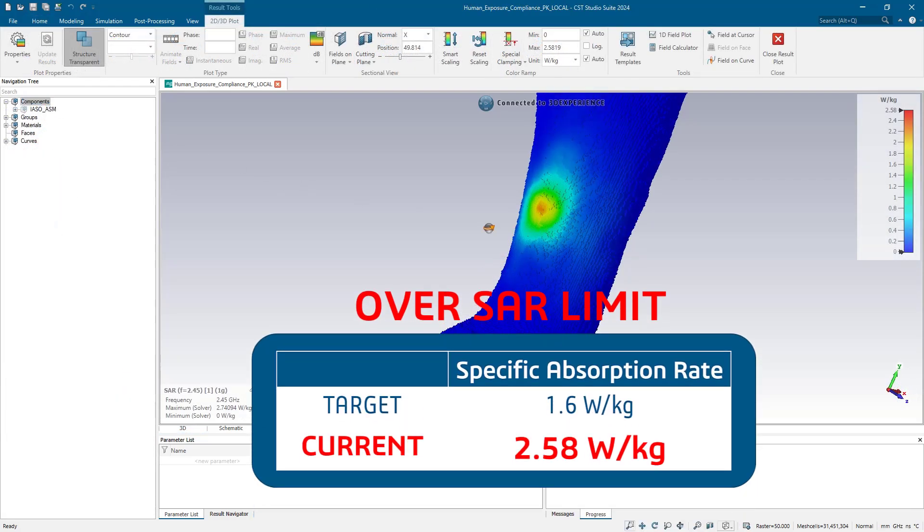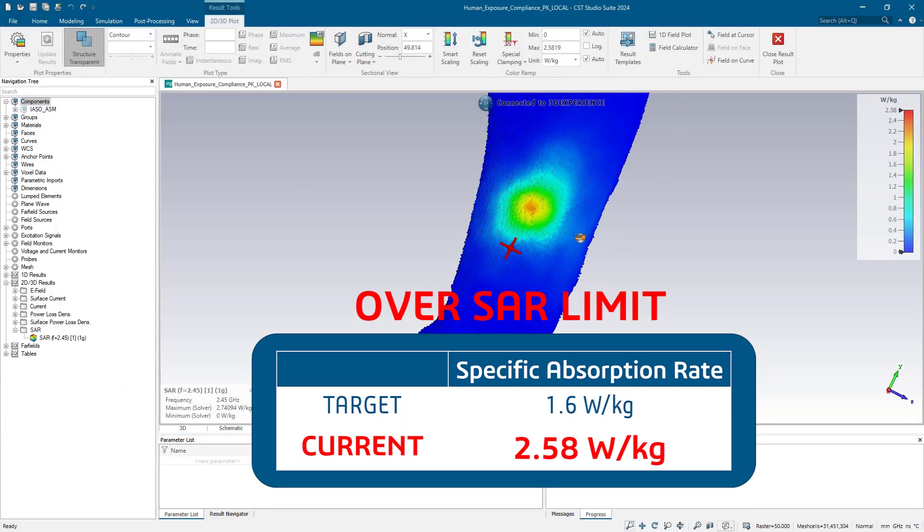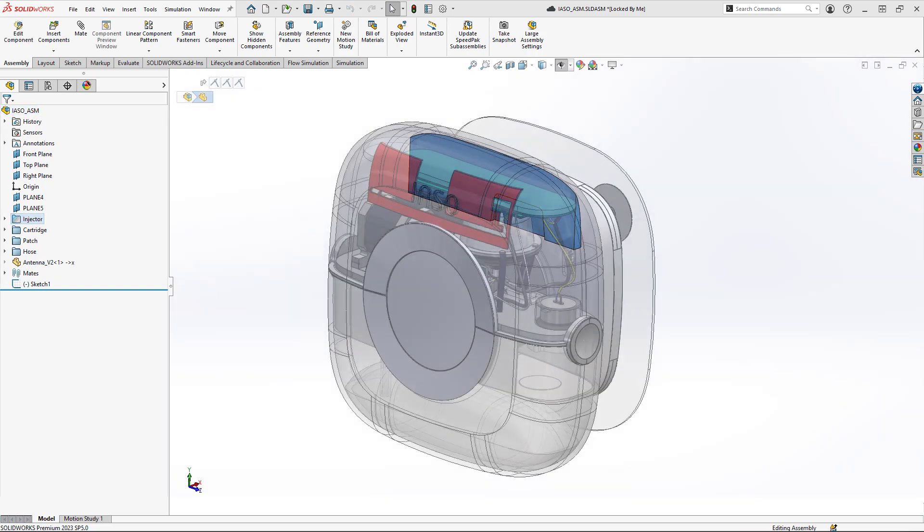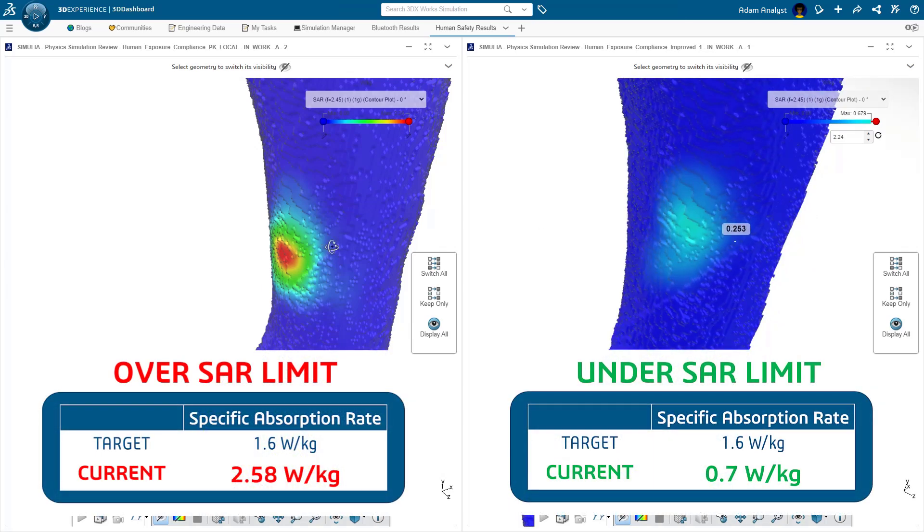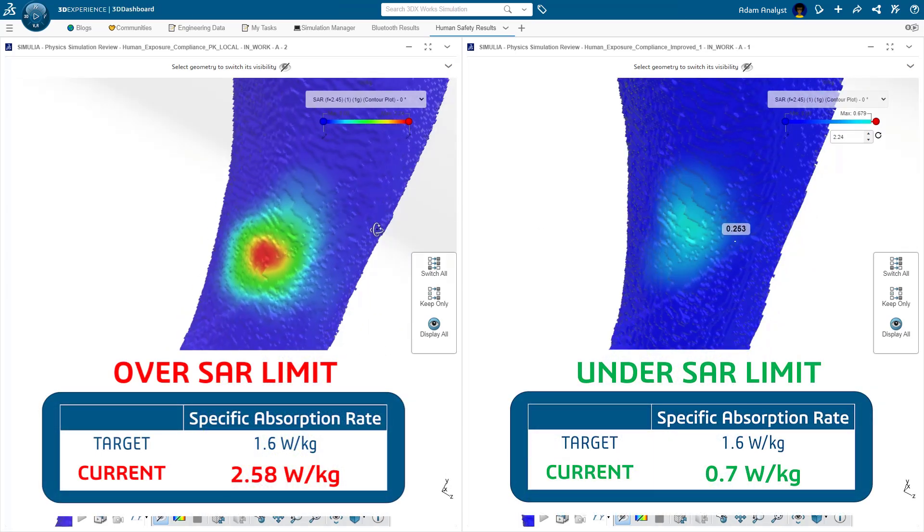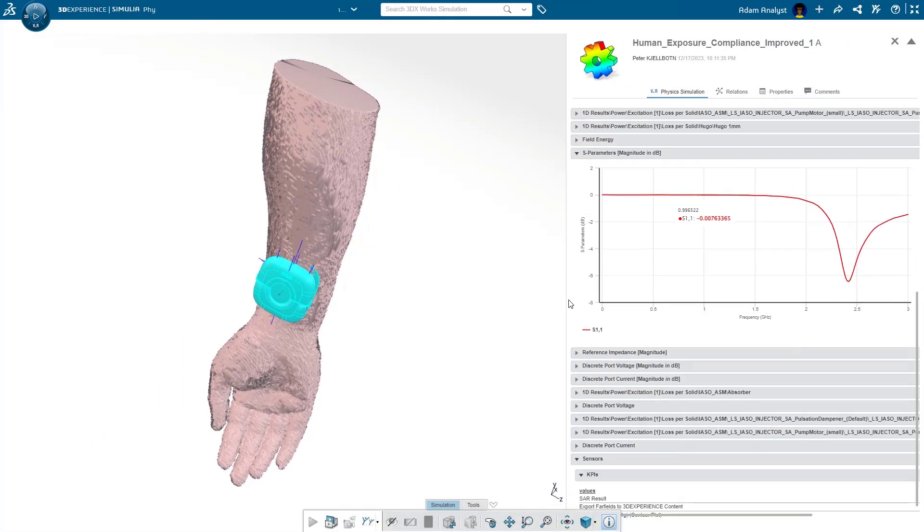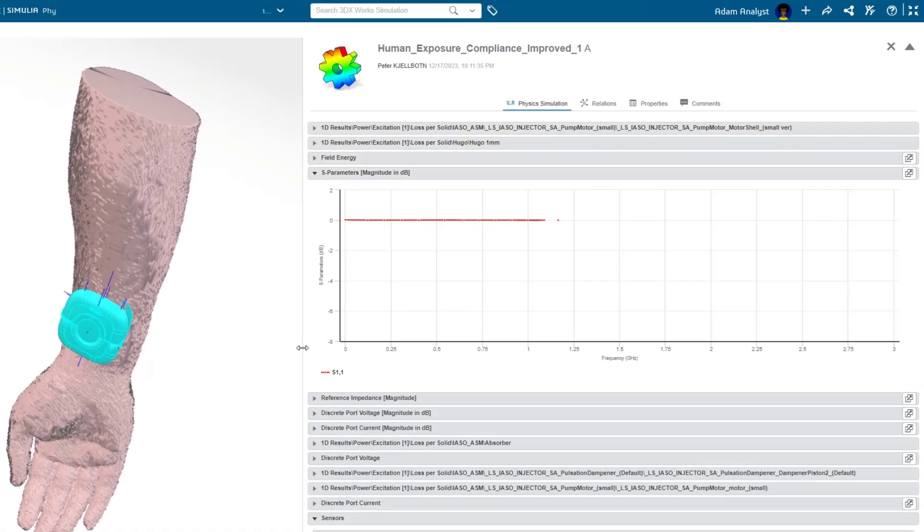In this case, we're over the allowable limit. No problem, we'll model an absorber in SOLIDWORKS and rerun the study. Now, the SAR is well under the allowable limit, but placing the absorber next to the antenna and placing the whole assembly next to the human arm can affect the antenna impedance.